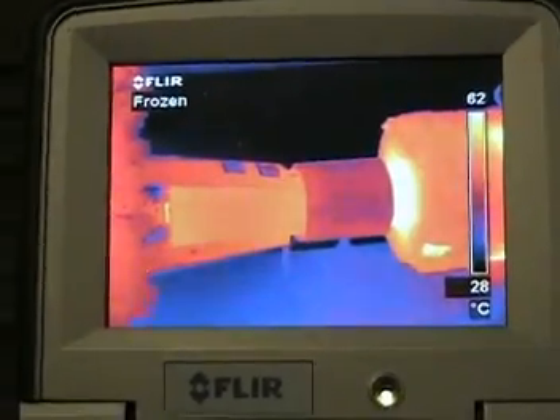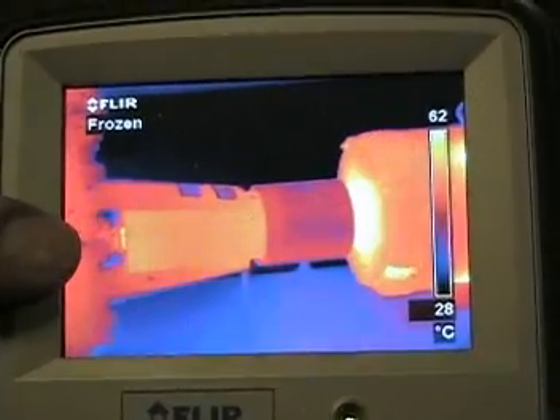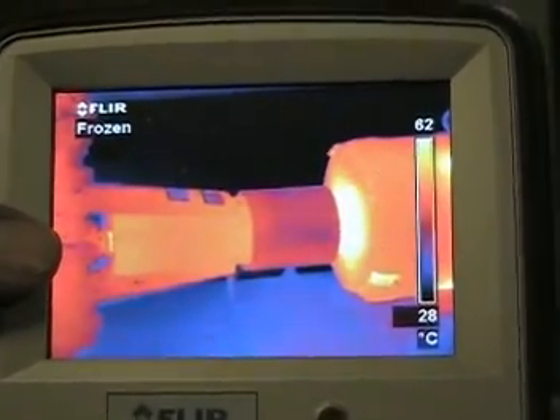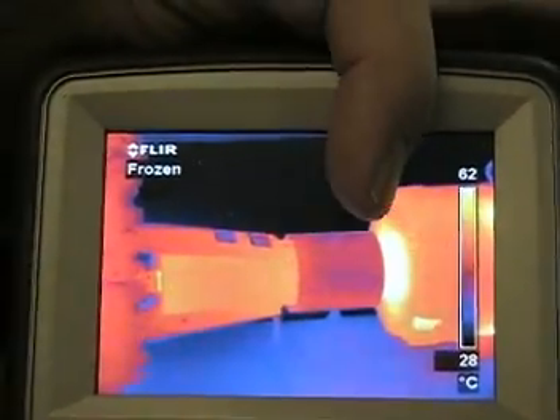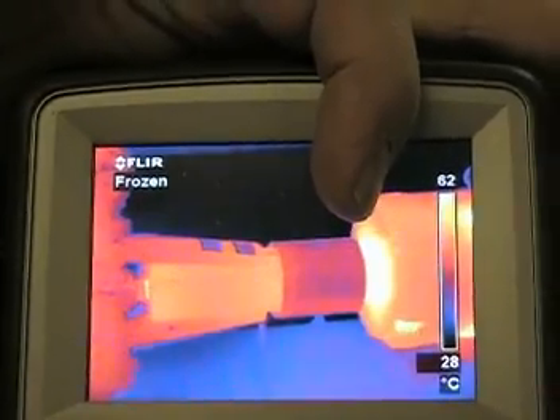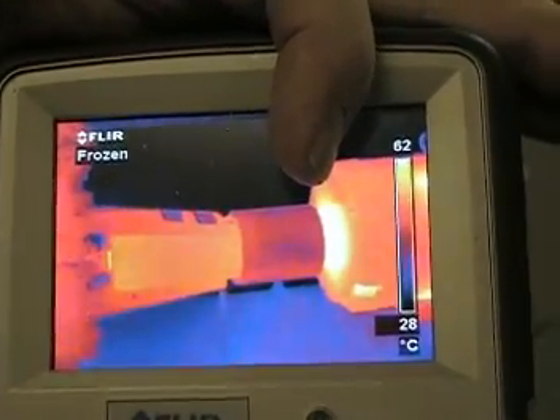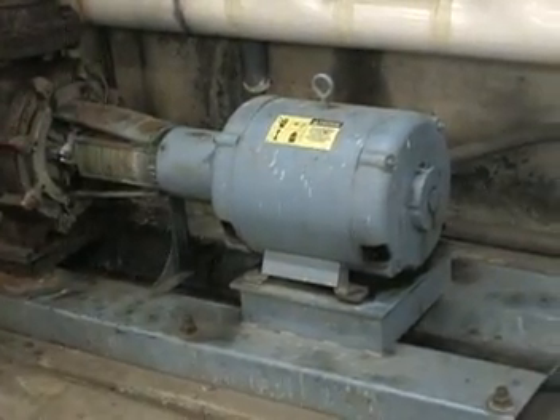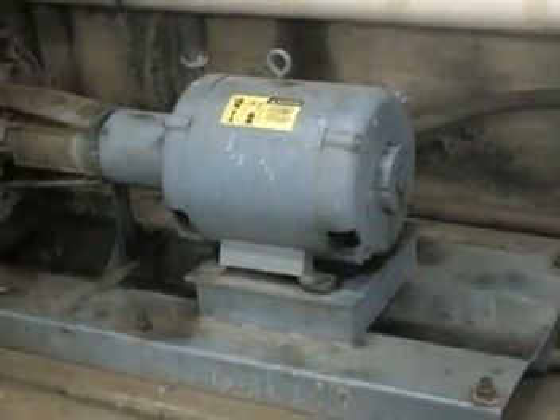The recommended solution is to check the coupling alignment between the pump and the motor. We will also check for proper lubrication. If these two factors are not the issue, then the recommended solution will be to replace the front bearing. Utilizing infrared and ultrasonic technologies, we clearly isolate the problem area on this motor.